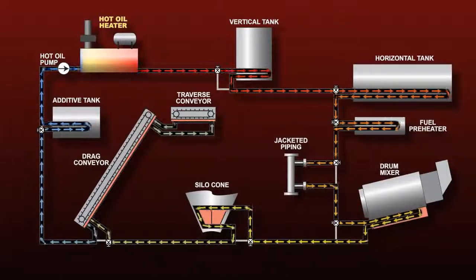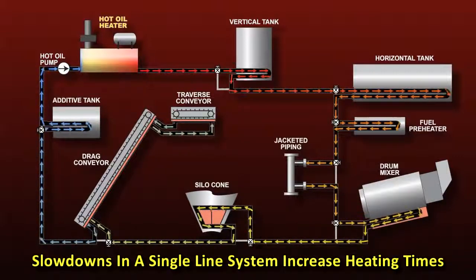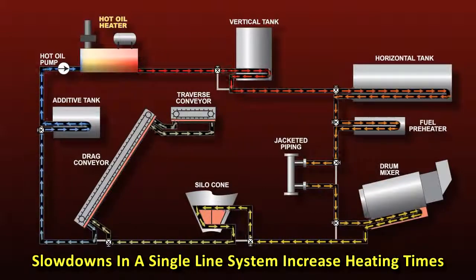But a number of components in series with each other create a lot of resistance to flow. This resistance dramatically slows down how fast the hot oil flows through the components and returns to the heater, and it noticeably increases the time needed to heat the components.